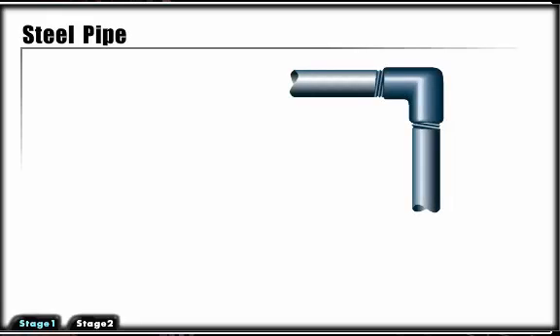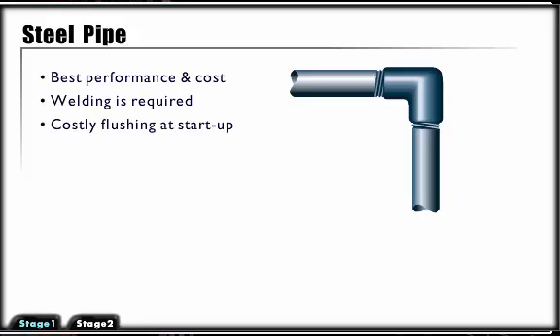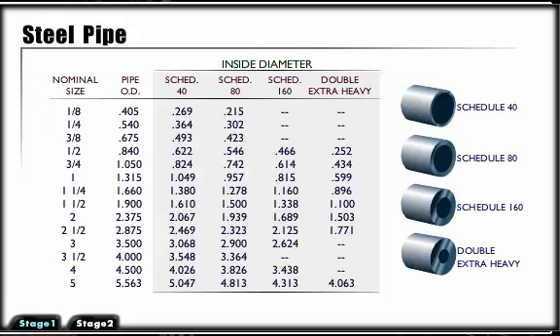Steel pipe is often a preferred conductor from the standpoint of performance and cost. However, it is often difficult to assemble because welding is required to give maximum leak protection. It also requires costly flushing to ensure a contaminant-free system at startup.